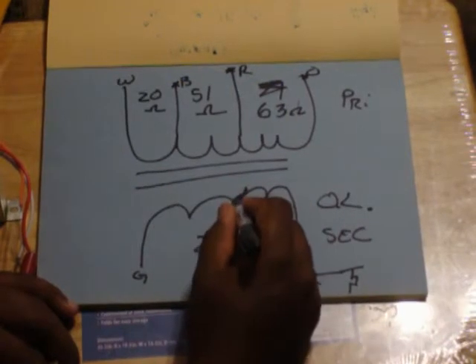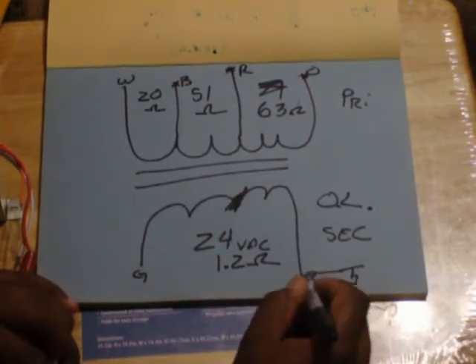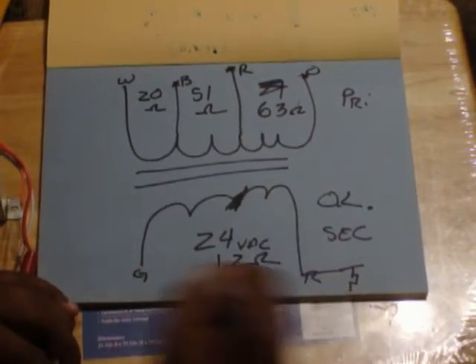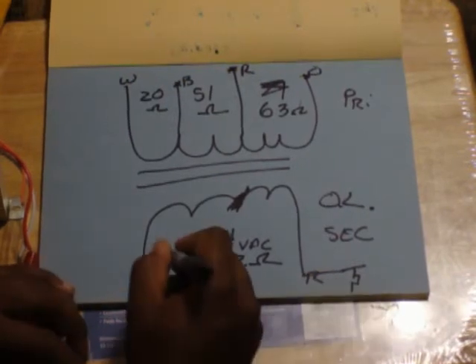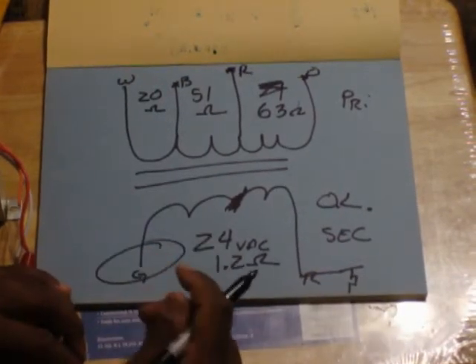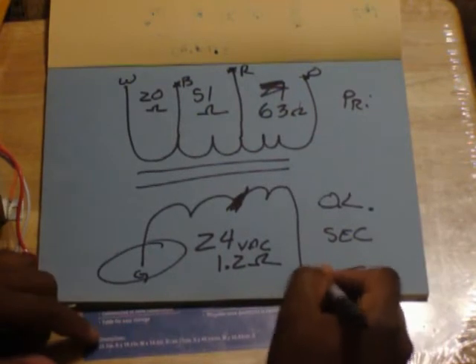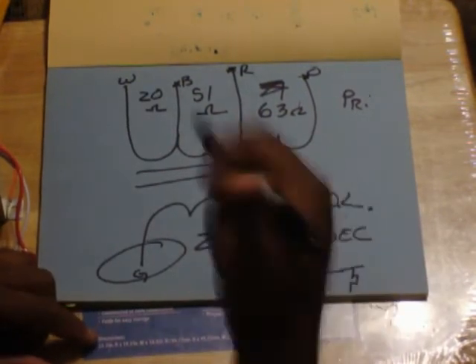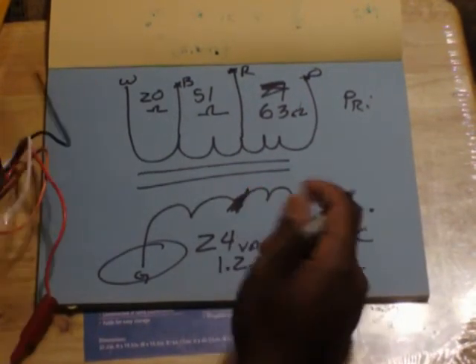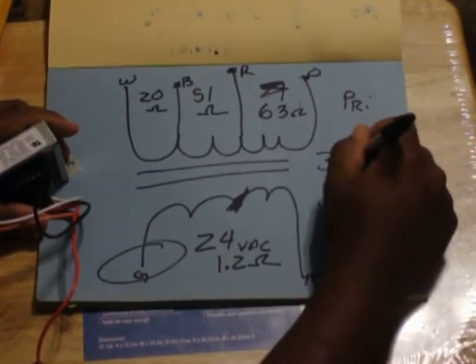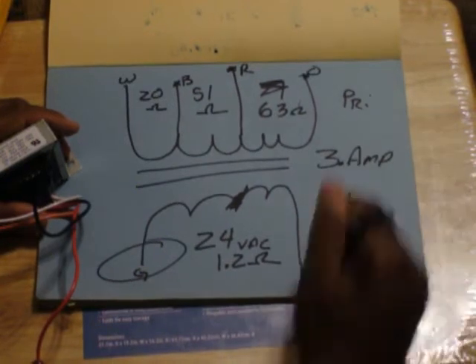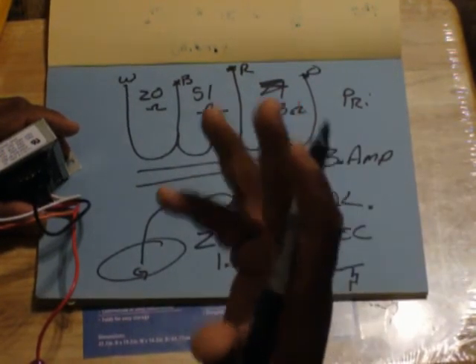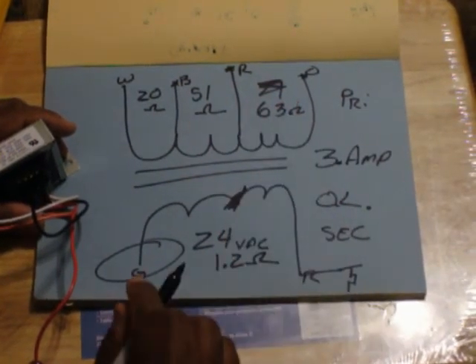So when you put in a new transformer and your secondary is burned, what I like to do is, before I hook up my red wire, get my amp meter ready, clip it over a wire here, and just touch the red wire where it's supposed to go, and see if your amp draw shoots up. A lot of transformers are only rated, they have a fuse on that goes off at 3 amps. So if you hook it up, you pull in 5, 6, 7, 8 amps, something's wrong. Very, very easy to check.